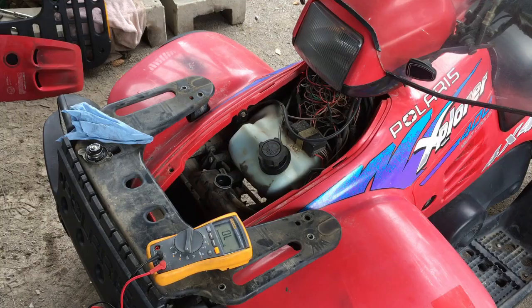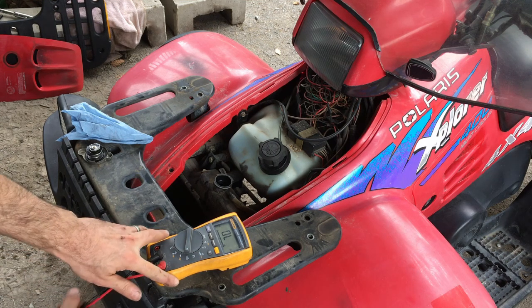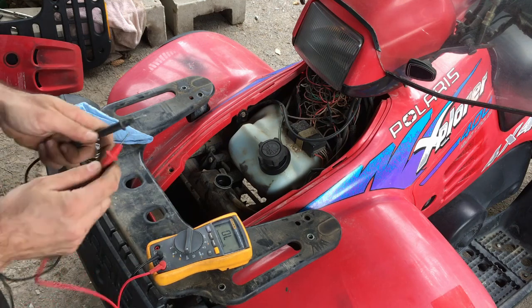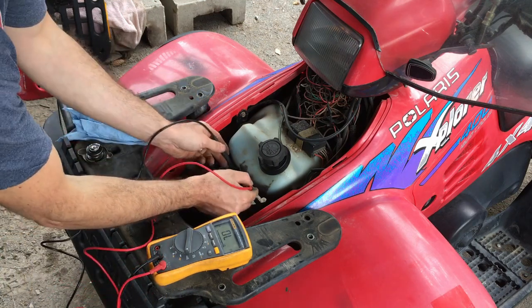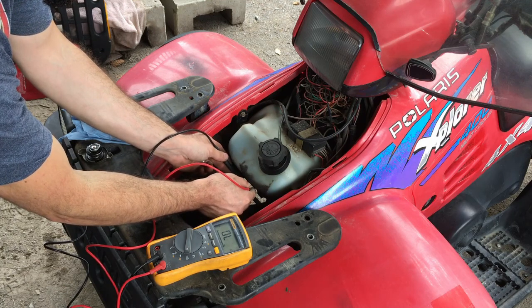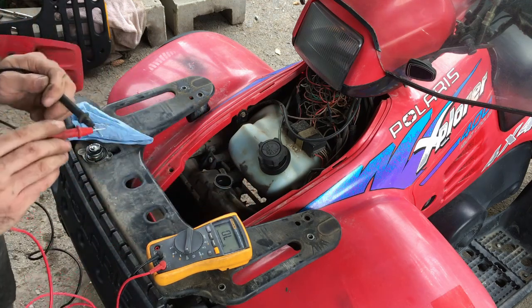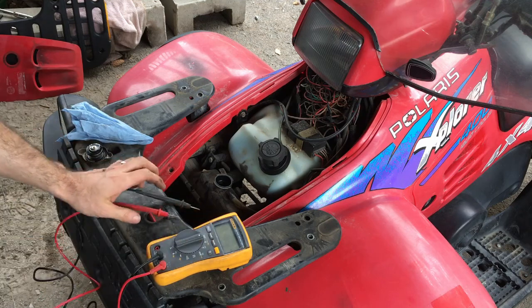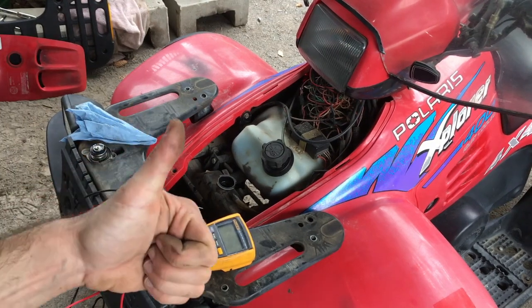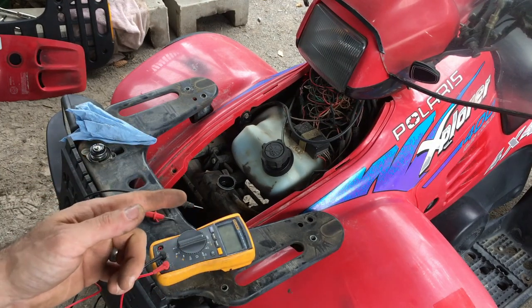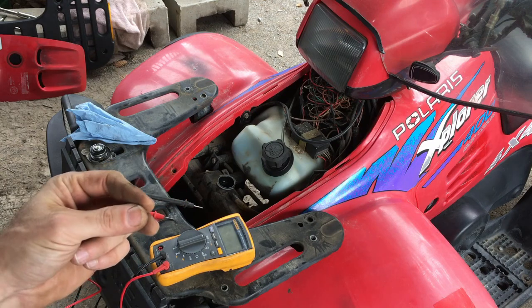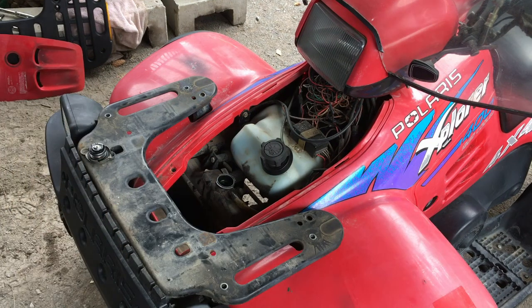Actually, before that, we'll check the continuity on that temperature sensor. It's supposed to be open right now and only closed once it reaches the temperature, so we'll see what it does. It's testing all right with the meter, but we're not sure if it actually closes when it's supposed to. We'll go ahead and remove the sensor now.